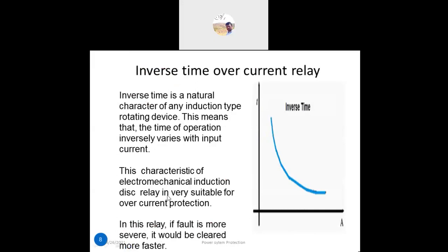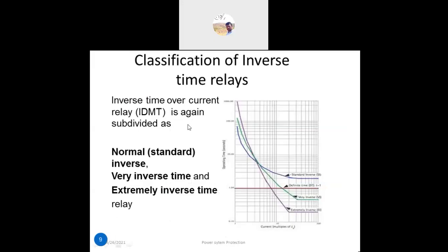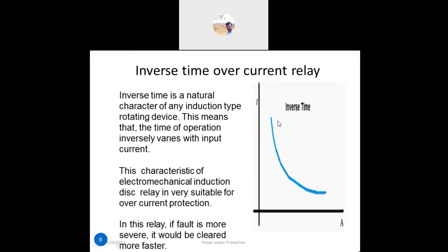If the fault current is high, the operating time will be very less. For example, if a fault occurs at 100 amperes, the trip time will be less. If the current is high, time will be less; if the current is low, time will be high — that is the inverse relationship with time. The pickup current remains the same; the operating time varies inversely with the input current.